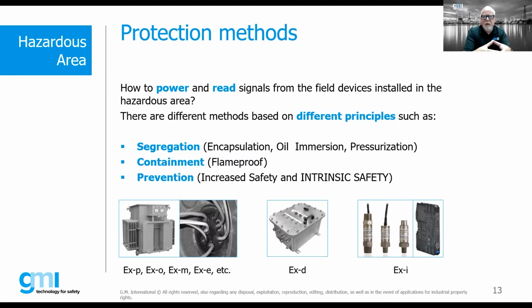And then, of course, prevention is basically saying, look, we're not going to have ignition sources on electrical equipment or instrumentation equipment within a hazardous area. The two most common methods of prevention are increased safety and certainly intrinsic safety, and they operate in a different fashion. Increased safety is more where we would have, say, high power terminals, and we have to have special creepage and clearance requirements. With intrinsic safety, we're talking about limiting the energy, but we can still have arcing or sparking type devices in a hazardous location. We designate Ex i as our concept for intrinsic safety.